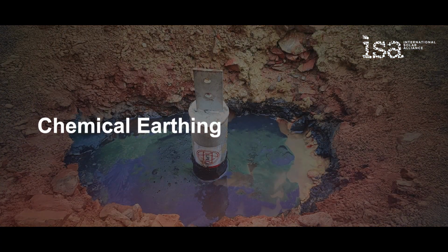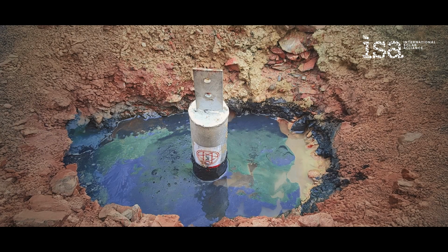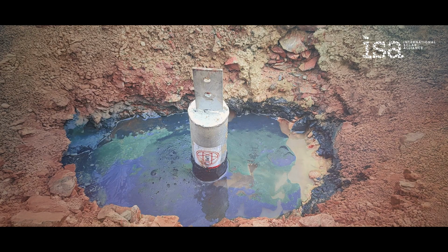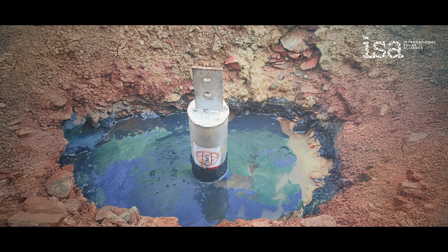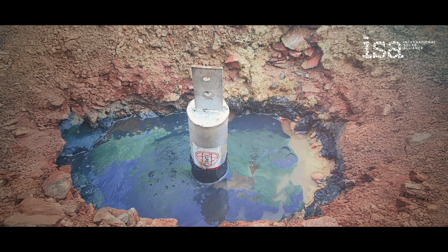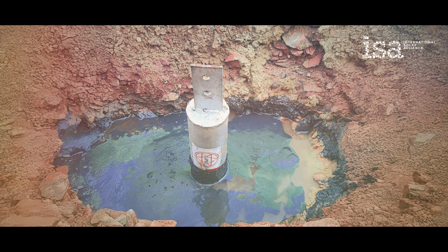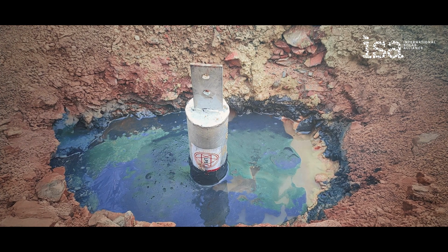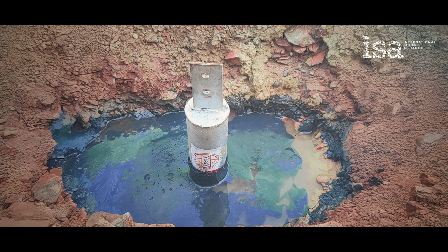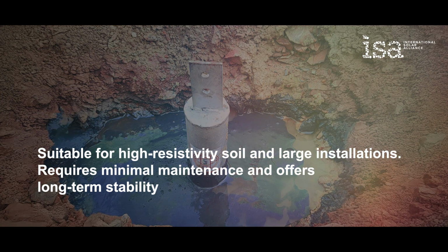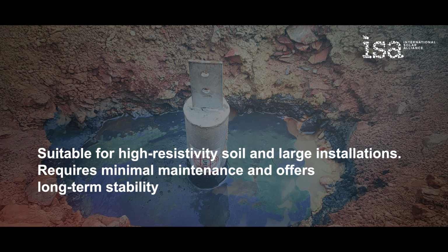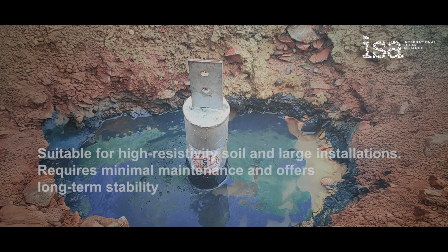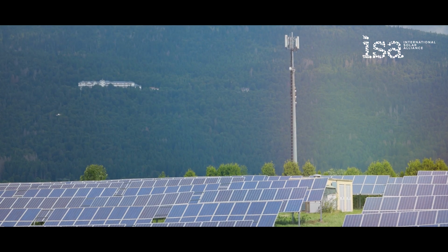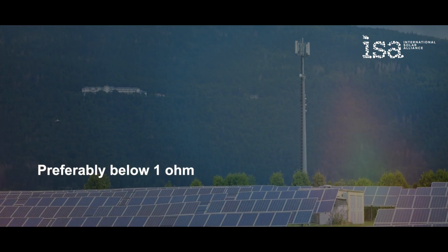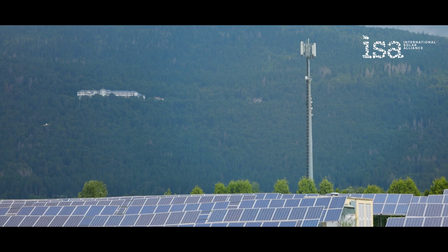Chemical earthing uses a chemical mixture such as bentonite, graphite, or salt to improve soil conductivity and maintain consistently low resistance in dry conditions. Chemical earthing is ideal for areas with high soil resistivity, requiring minimal maintenance and ensuring stable resistance throughout the year. Suitable for high resistivity soil and large installations. Requires minimal maintenance and offers long-term stability. An effective earthing system should have low resistance, preferably below 1 ohm for large plants, and ensure quick dissipation of fault currents.